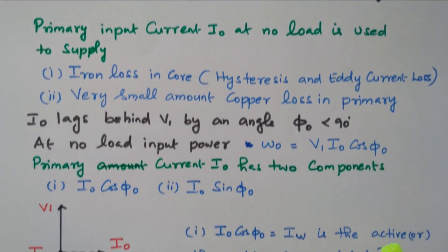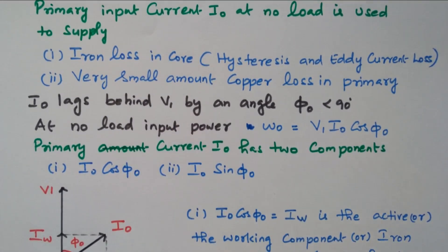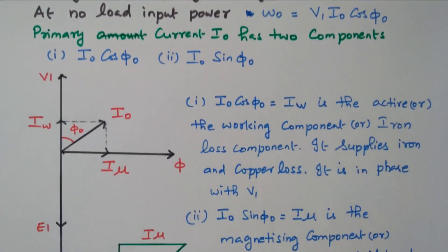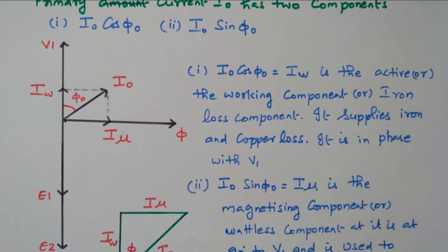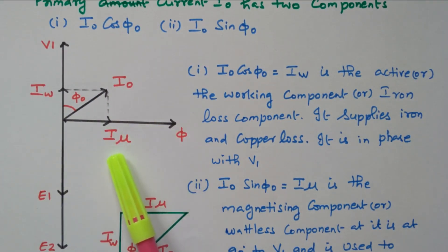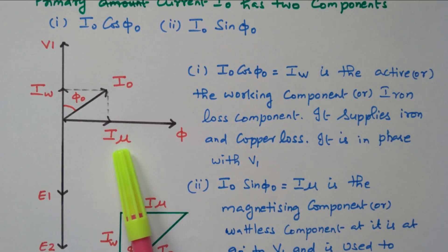Now I0 is split into two components by referring to the vector diagram: I0·cos(phi0) and I0·sin(phi0). Looking at the vector diagram, this is the flux and the magnetizing current. I0 is split into two parts — magnetizing current and working current. The magnetizing current flows due to the flux; due to magnetizing current only the flux is produced, so both are in phase.